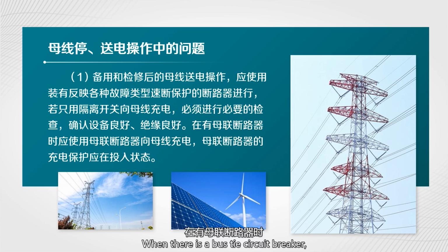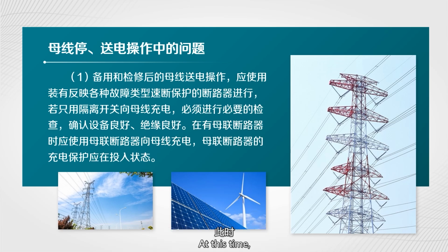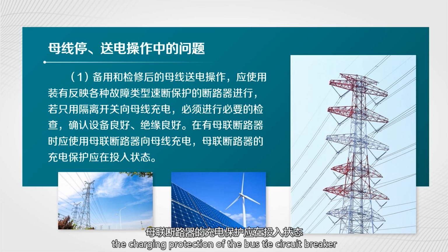When there is a bus tie circuit breaker, the bus tie circuit breaker should be used to charge the busbar. At this time, the charging protection of the bus tie circuit breaker should be in the operational state.